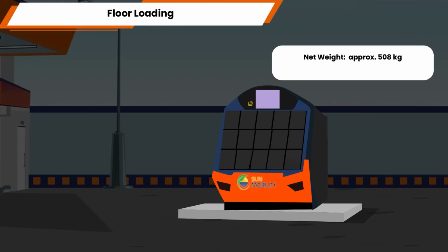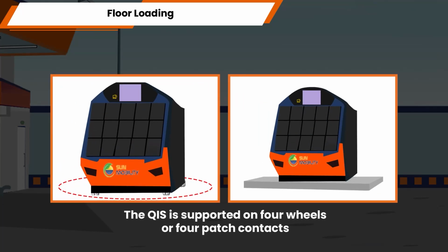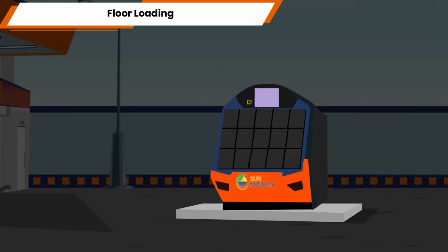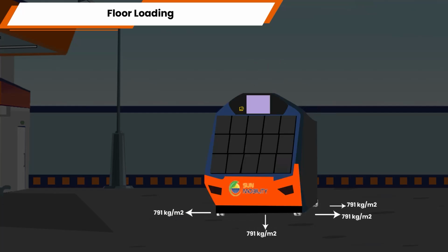Floor loading: QIS net weight approximately 508 kilograms, QIS maximum gross weight approximately 700 kilograms. The QIS is supported on 4 wheels or 4 patch contacts. The floor needs to sustain QIS movement at 0.5 meters per second during deployment. For all other cases, QIS is a stationary load with the following load specifications: uniformly distributed load 791 kilograms per meter square. For a distributed center of gravity, the worst case static point load across front and rear wheels is 210 and 140 kgs per wheel respectively.